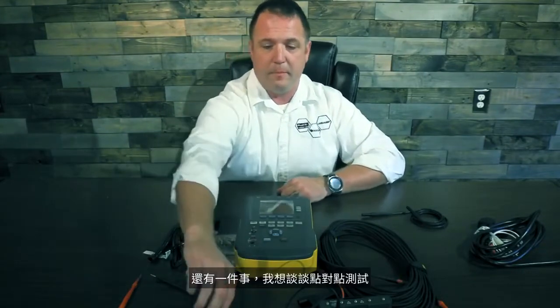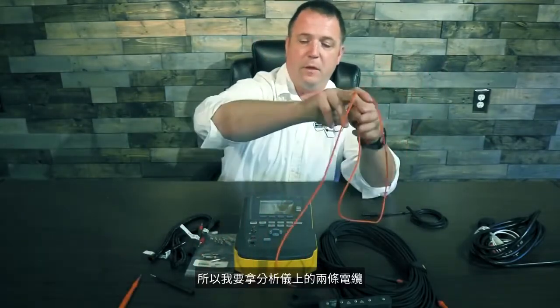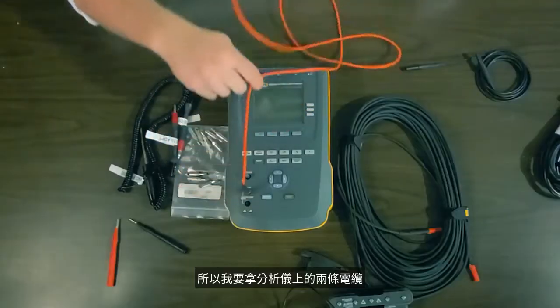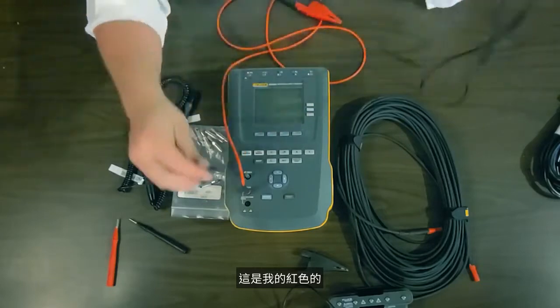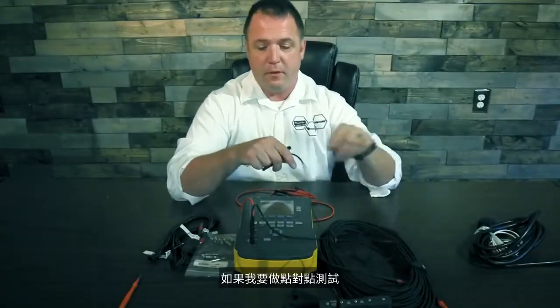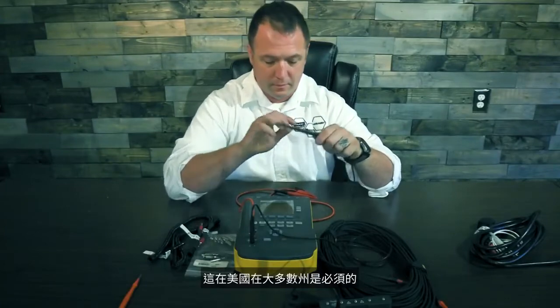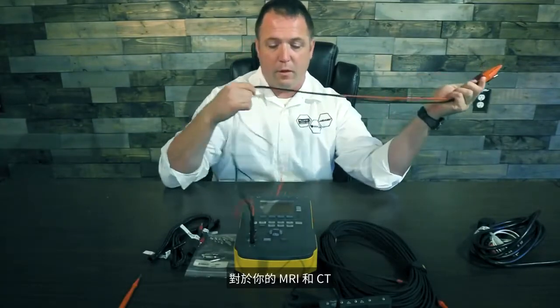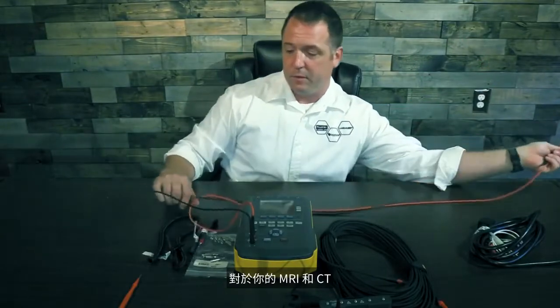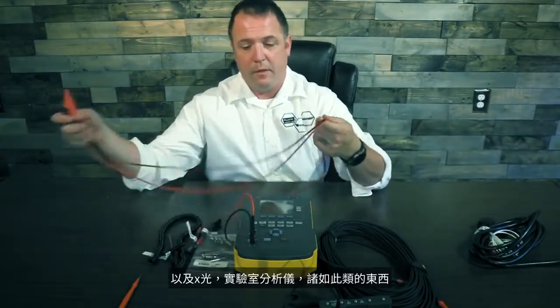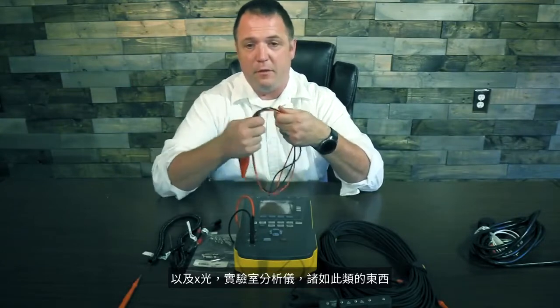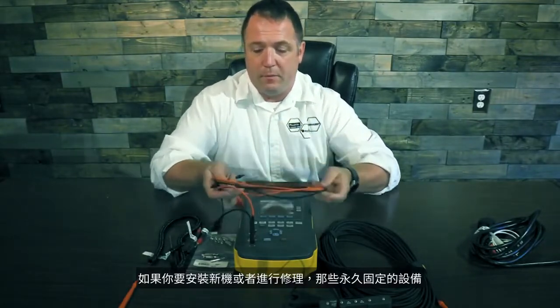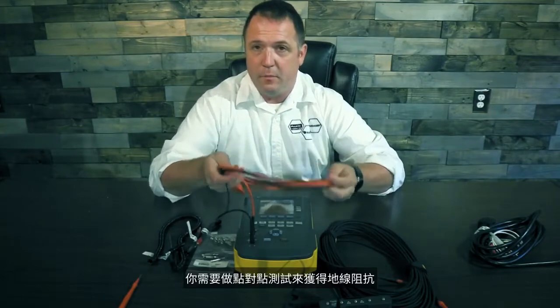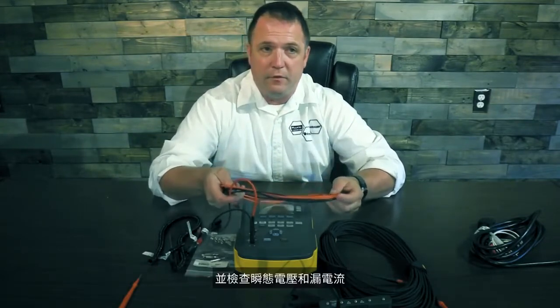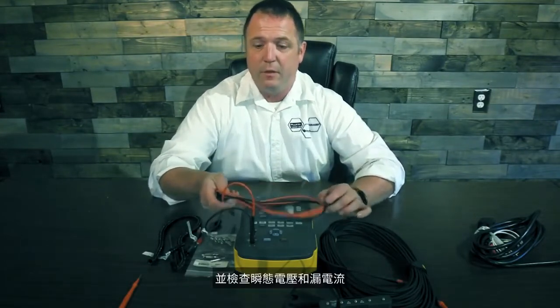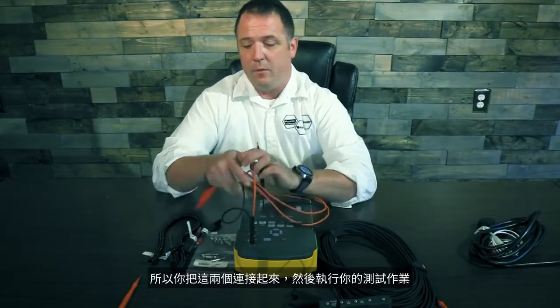One more thing I'd like to talk about, point-to-point testing. So I'm going to grab the 2 cables that come with the safety analyzer. There's my red one, here's my black one. If I was going to do point-to-point testing, this is something that's required in most states in the United States on your MRI tables, your CT tables, X-ray tables, lab analyzers, things like that. If you're going to do a new one or do a repair of one, those permanently fixed devices, you're going to need to do point-to-point testing to get the ground wire resistance and check for transient voltages and leakages. So you connect these 2 in here, and then you go and do your testing.